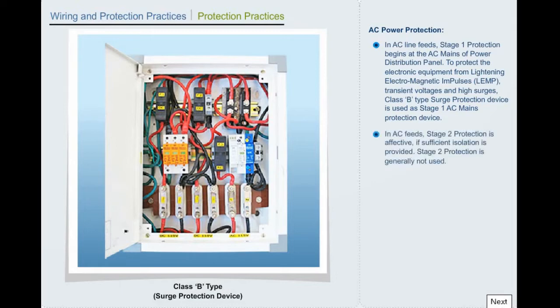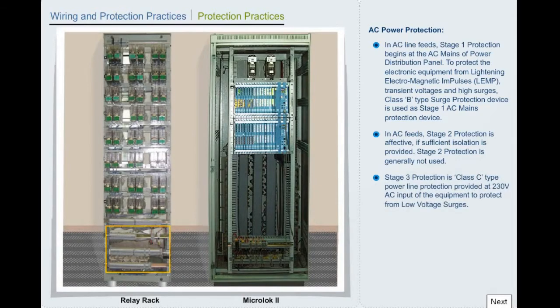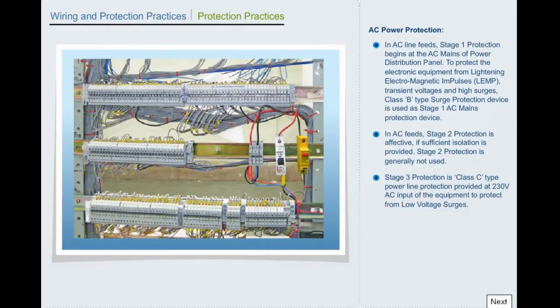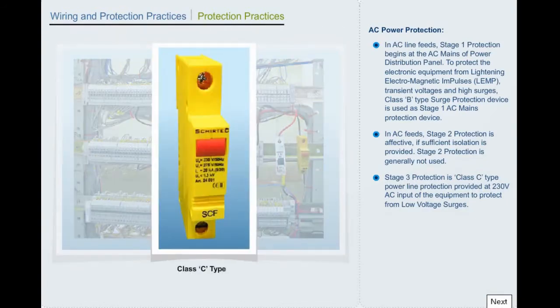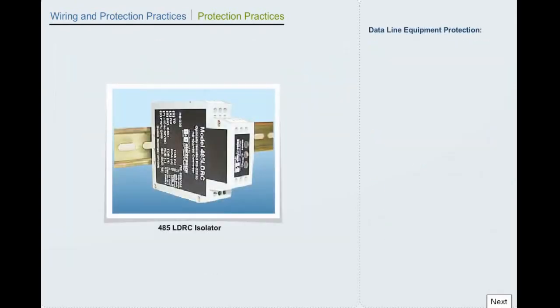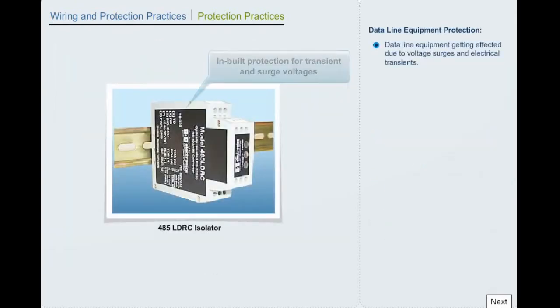protection device. In AC feeds, Stage 2 protection is effective if sufficient isolation is provided. Stage 2 protection is generally not used. Stage 3 protection is Class C type power line protection provided at 230 volts AC input of the equipment to protect from low voltage surges. Surge suppressor is provided at 230 volts AC input of the equipment such as operator PC and maintenance PC. Data line equipment getting affected due to voltage surges and electrical transients.